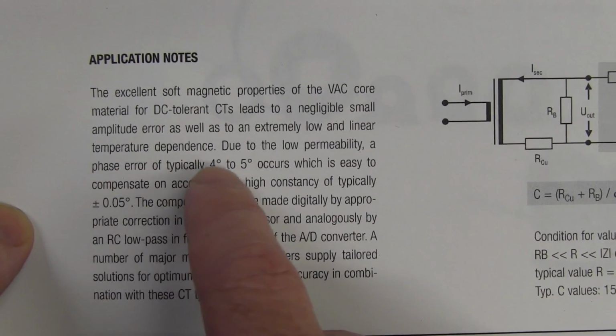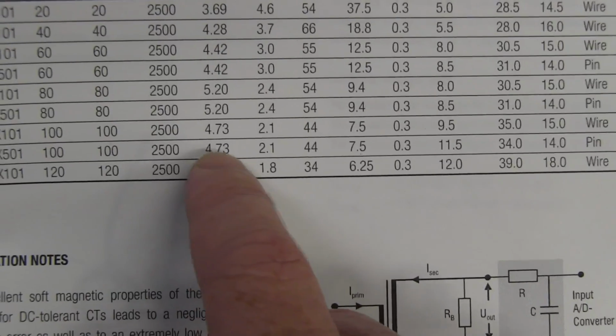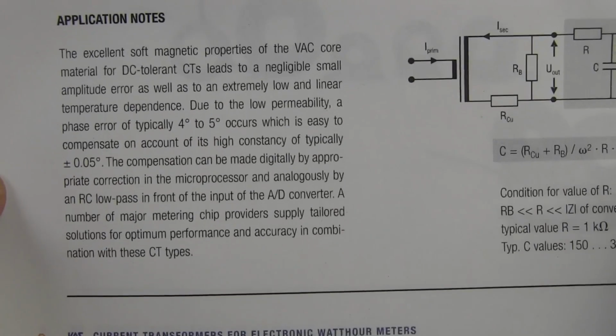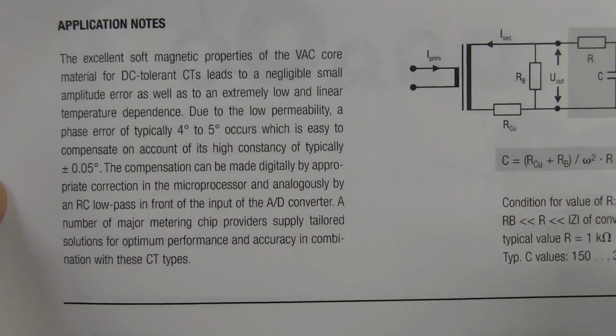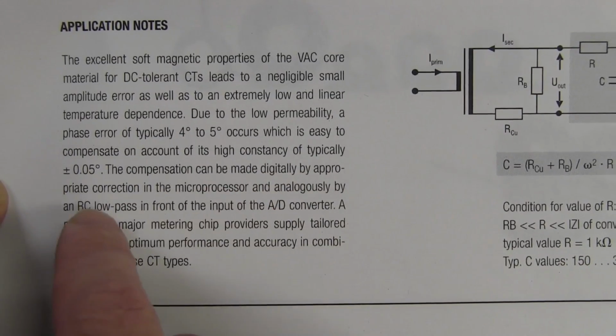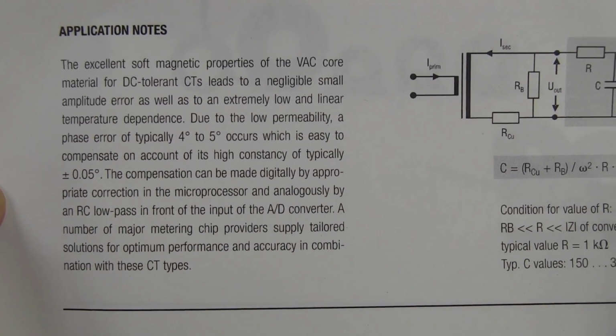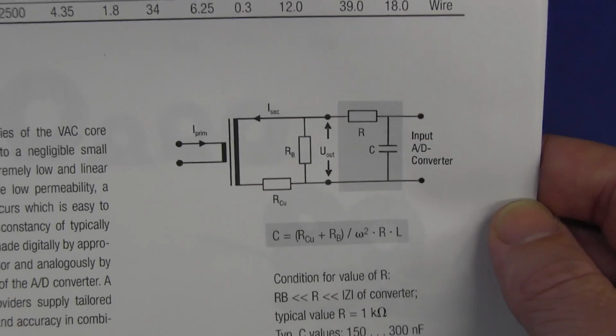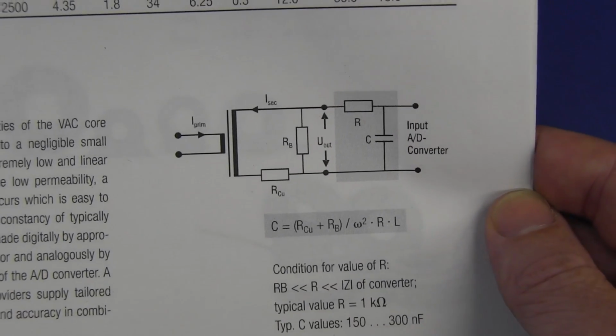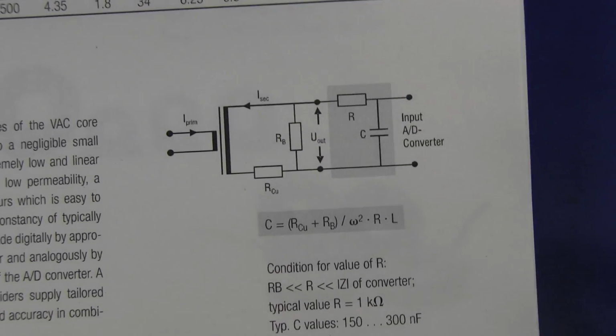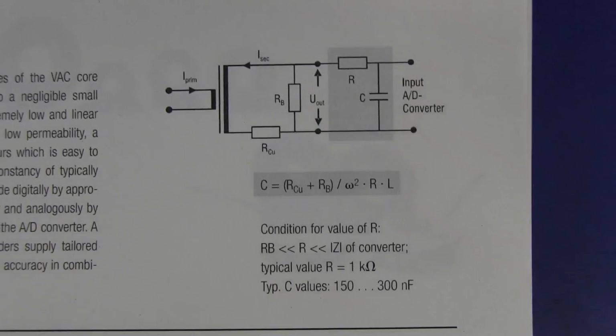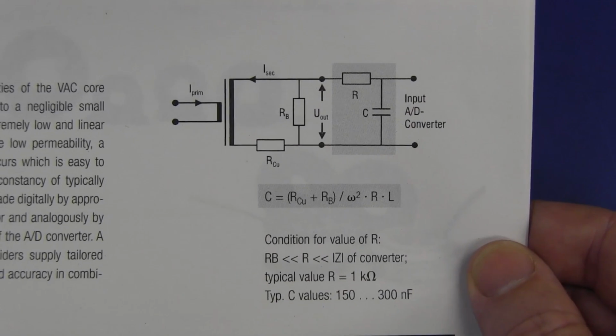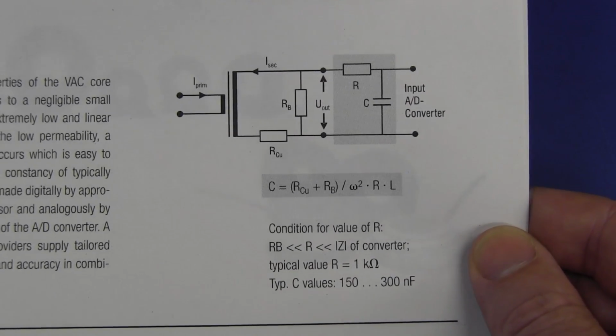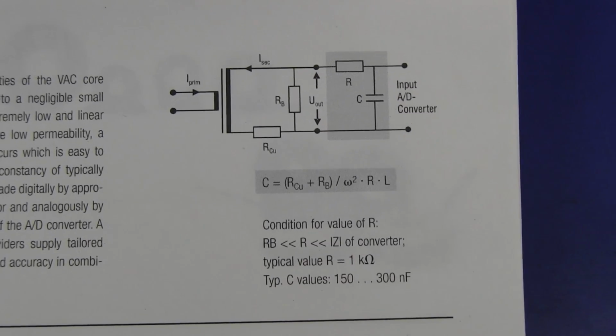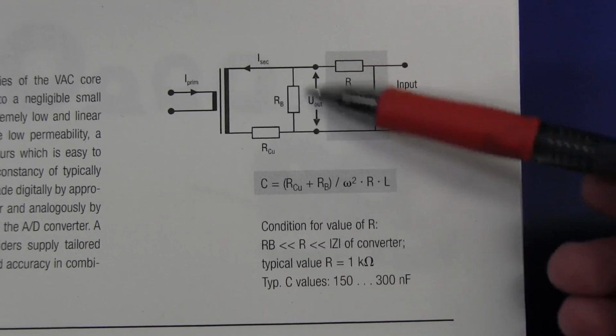Due to the low permeability of the core material, the phase error is typically 4 to 5 degrees, and there it is, 4.73, specified precisely. Of course, you can calibrate that out, either in software or in the RC low pass filter. My guess is they're probably doing it in software because that's the easiest way. Once this thing is already installed and assembled, they would individually calibrate each one to remove that error. And here's those components I showed you earlier on the output there.